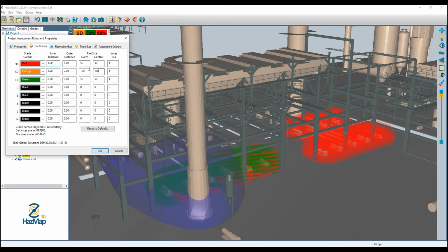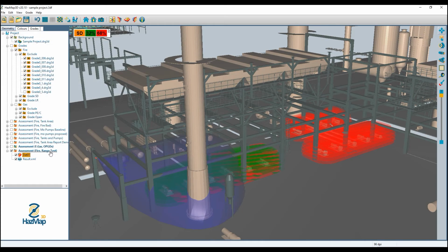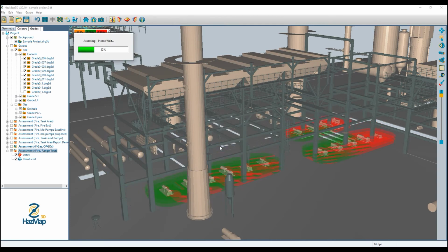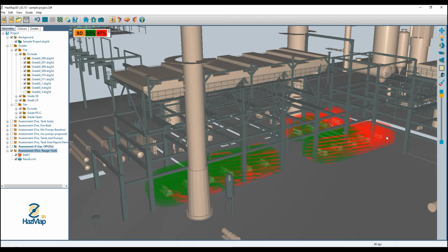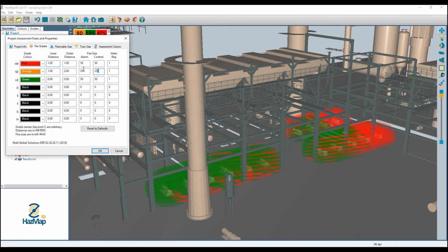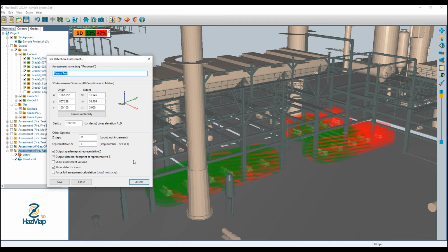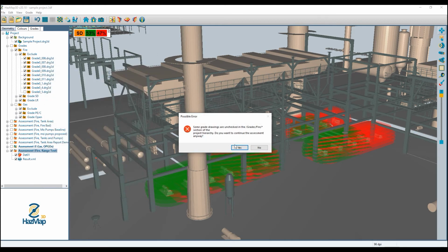If I increase again, say to 250, and I'm just increasing the requirement for alarm and control action at the same time, I can set different fire sizes for alarm and control action if I want to. I can now see I've more than doubled the size of the fire again, so now I've gotten another 40+% boost in range. And now if I do one final increase to 500 and run again, because I've increased the target fire size by a factor of 10, I'm going to get a roughly 3x increase in my range.